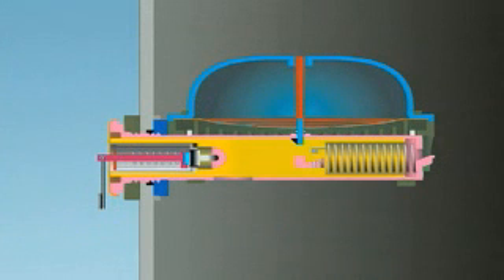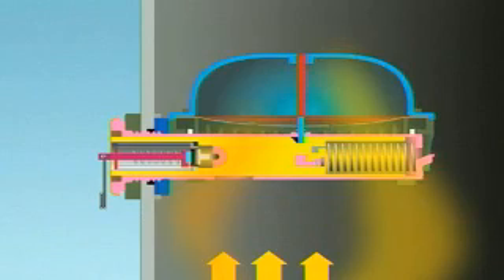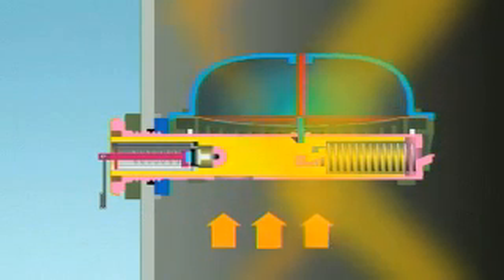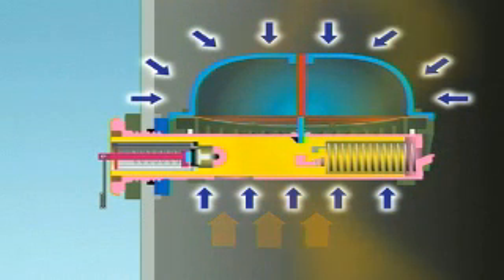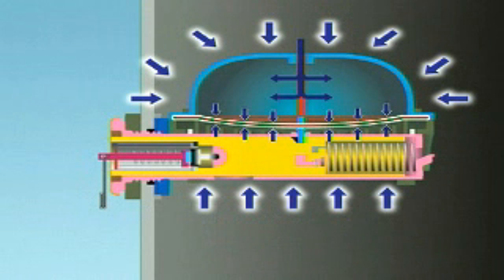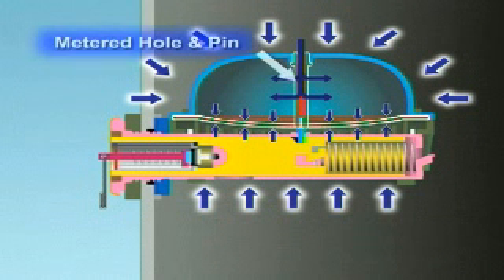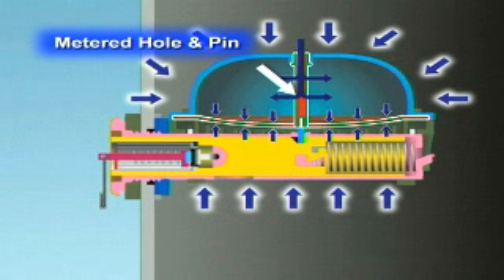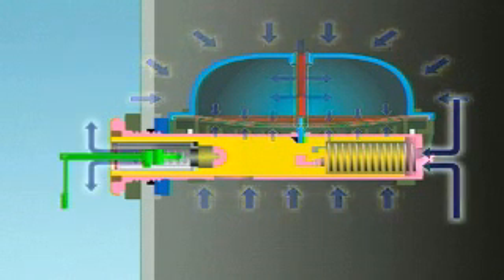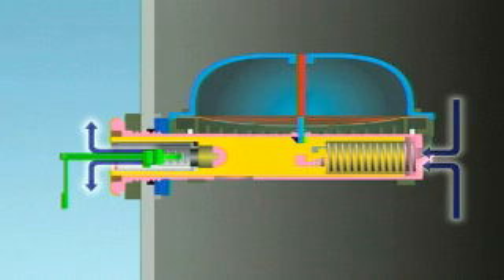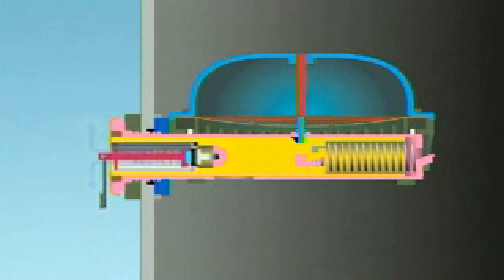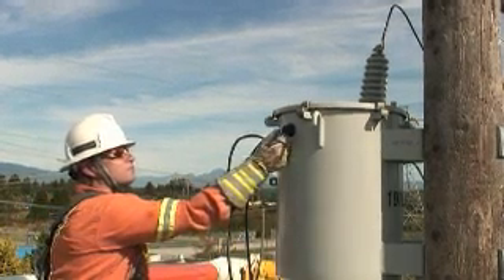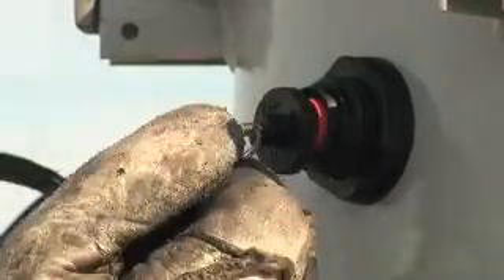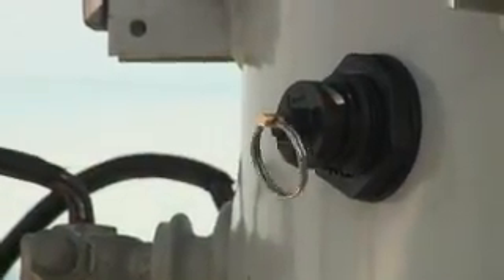During hot days or under heavy loads, the transformer will heat up, and the pressure inside the transformer tank will gradually increase. As the pressure gradually increases, it can equalize on each side of the IFD's diaphragm through a metered hole. When the PRV activation level is reached, the PRV opens, allowing air to escape. It closes when the pressure is reduced. The IFD PRV can also be operated manually, just like other transformer pressure relief valves.